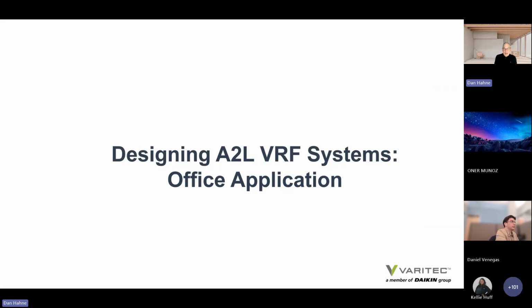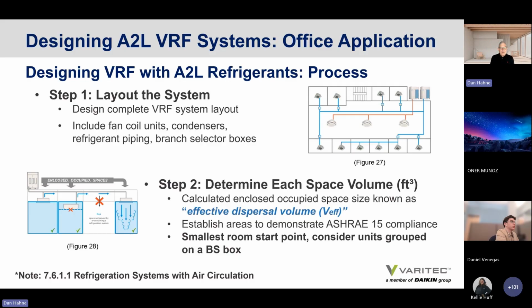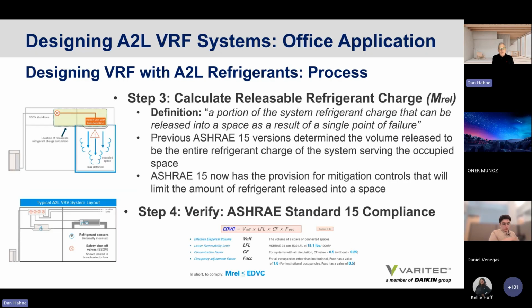So let's look at a design of an A2L refrigerant for an office. First, let's look at the steps for laying this out. The first thing you need to do is lay out a system. The second thing you need to do is determine the space volume of each zone served by the system and understand what the smallest room is in its volume as the start point for what the maximum refrigerant concentration limit is in that actual system and how it's to be controlled. You then calculate the releasable refrigerant charge and then determine whether or not the releasable refrigerant charge meets or is less than the effective dispersal volume charge assigned to the space. If it exceeds it, it does not comply. If it's less than, it does comply.